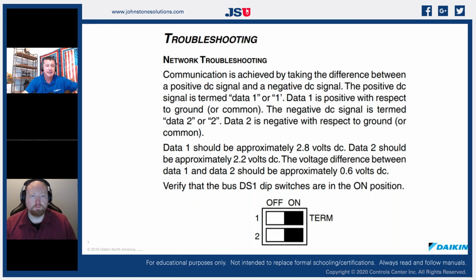Anytime we have long lengths of wire, we're going to have a voltage drop. So we could potentially lose some of our voltage and get down below 0.6. Or say I add a zone control panel. If I add a zone control panel, I'm adding an additional smart, communicating thermostat, so I'm adding more load to my network. So I have the potential for my bias to go down below 0.6 volts. Hopefully it doesn't. Hopefully I fire this thing up and I have 0.6 volts bias between those. If I don't, now I have to do something about it.